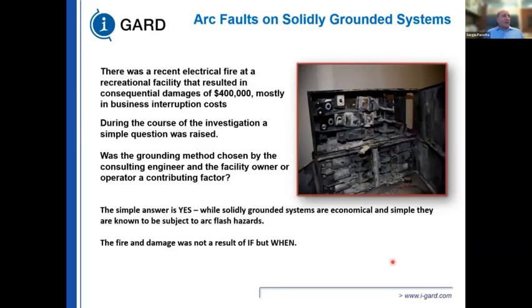Here is an example of a single phase to ground fault that propagated to a three-phase fault very quickly, and it caused $400,000 in damage. Well, this one was much, much more, because what happens now is you lose your electrical switchgear, your main distribution system, so that has to come out and be replaced. You're on generation for a little while, and now we haven't taken into effect the impact on your business. We've only looked at the cost of replacing the equipment and modifying your electrical system so you can run temporarily until you get new equipment.